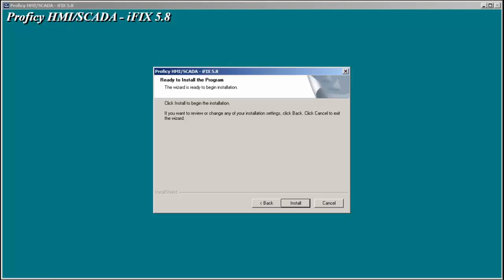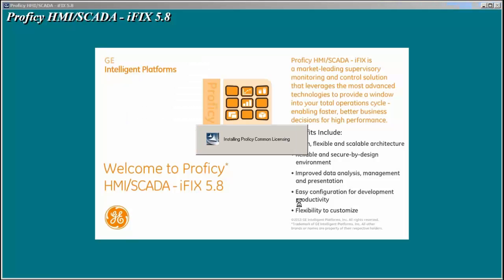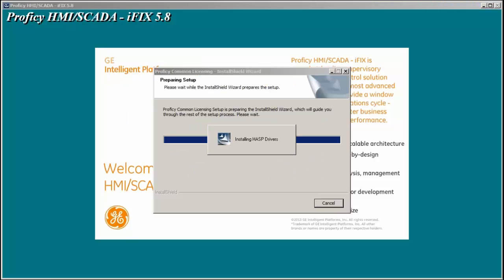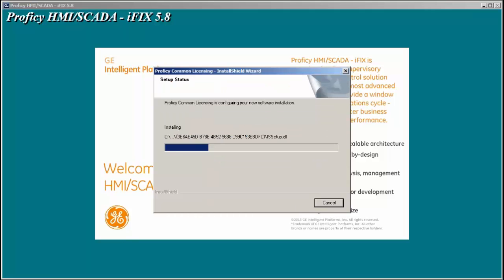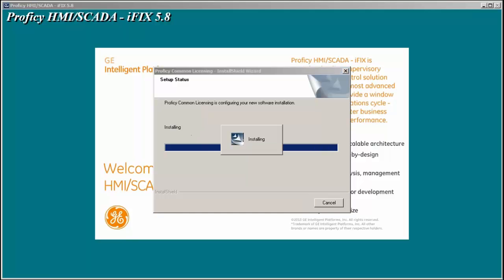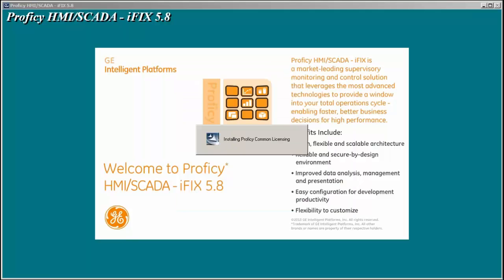And we'll hit install. As you'll notice, GE will install all the components that it needs to be any version of iFix, whether it's a SCADA node, a view node, a terminal server machine, etc. It does install all the software needed to be any of those components. It is controlled by what key is on the system and what options are selected under the system configuration utility. But those changes can be made at any point in time.